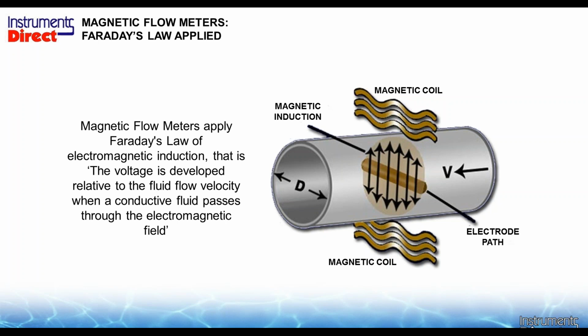Hence, we use the term Faraday's laws of magnetic induction, which basically states the operation of a magnetic flow meter, or a mag meter as we call them, is based upon Faraday's law. Basically, the voltage induced across any conductor as it moves at right angles through a magnetic field is proportional to the velocity of that conductor. And what in the world does that mean? Let's look at our diagram here.